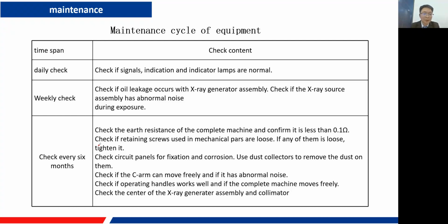And the next check is the screws used in machine are loose. If any of them are loose, tighten it. Check the circuit panels for fixation and corrosion. Use dust collectors to remove the dust on them. And also we need to check the C-arm can move freely and if it has abnormal noise.